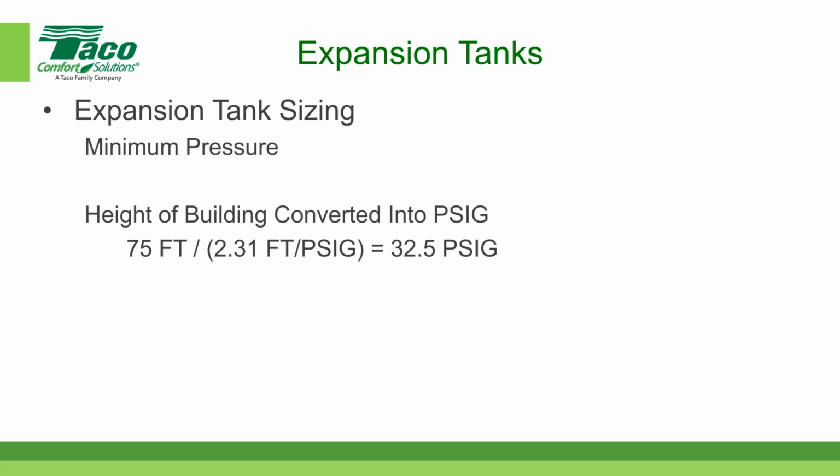We haven't pressurized anything. The valve is still open. All we did was fill the piping system. All the air came out, and eventually we got one little drop of water out of our valve that was located at the top of the building. So the next question is, how much pressure do we want when we close off that valve at the top of the building? So use your imagination for a moment. We close the valve off at the top of the building and we start to pressurize the system, but what pressure do we want at the top of the building?